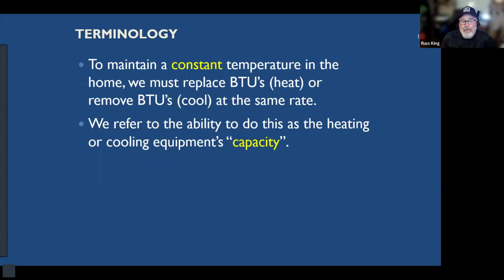So to maintain a constant temperature inside of a house, we want our house to stay at a certain temperature when it's really cold outside, and we want it to stay at a certain temperature when it's really hot outside. And those are actually two different temperatures. It's kind of interesting. In the summertime, 75 is typically good. That's a design temperature. And in the wintertime, 70 is what we like. But we can calculate that. And for that temperature to be constant, we have to be able to add BTUs at least the same rate they're escaping, or remove BTUs at least the same rate they're coming in. And so that's where the load calculation is important.